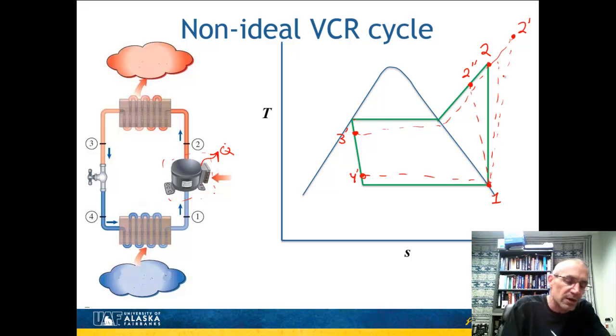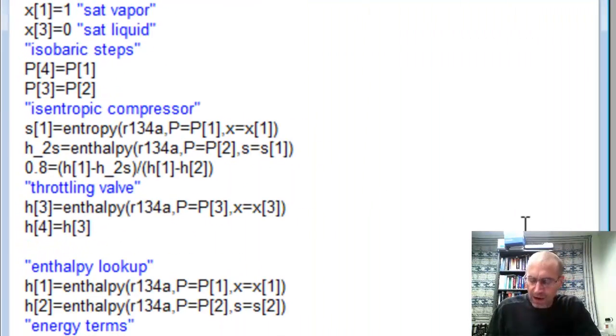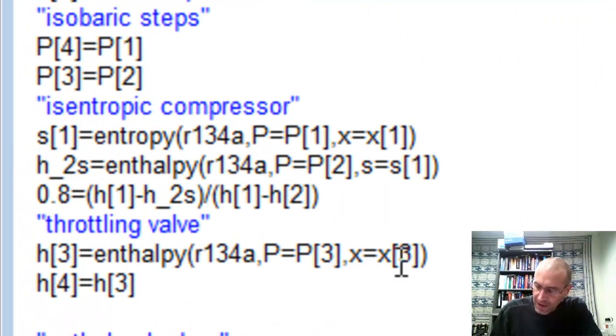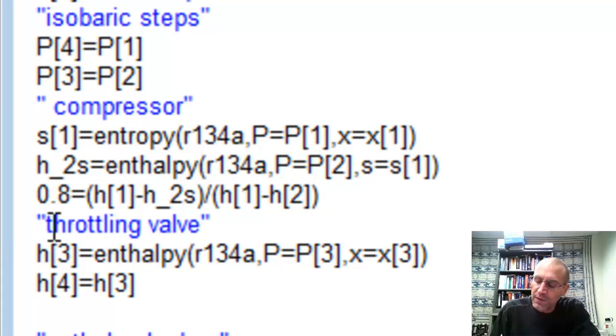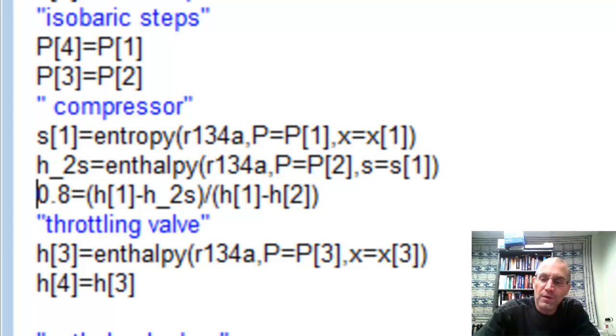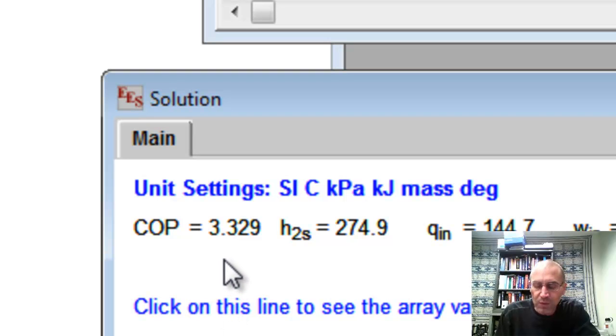To quantitatively examine these effects, let's look at the inefficient compressor in EES. I've added an 80% efficient compressor. Instead of setting S2 equal to S1, I now find the isentropic enthalpy and then apply the 80% efficiency to get the actual enthalpy at H2. Everything else stays the same — we're just isolating the effect of compressor efficiency. Solving this, the COP has dropped from about 4.1 to 3.3 — a pretty marked change due to compressor efficiency.